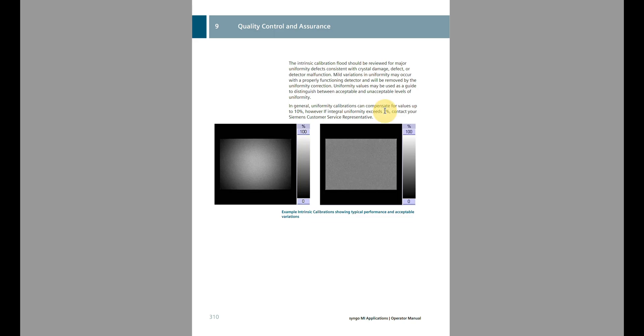The intrinsic calibration also has its own criteria. The calibration can compensate for values up to about 10%, but if you exceed 7% on the calibration — not the verification, but the high-count calibration — you need to contact service. If the intrinsic calibration passes and you're below 7%, rerun your intrinsic verification or daily flood and see if it now passes. If you're still not passing, that's the point to contact service or your physicist to get direction on meeting the manufacturer-stated specifications.